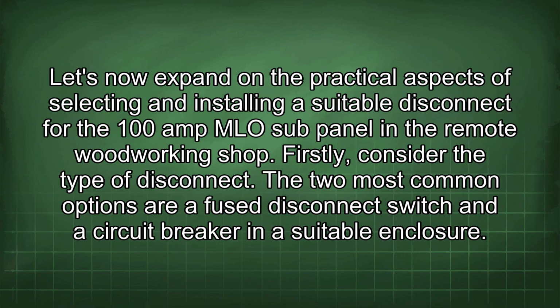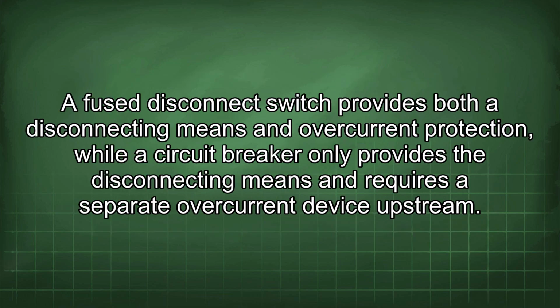Let's now expand on the practical aspects of selecting and installing a suitable disconnect for the 100 amp sub-panel in the remote woodworking shop. Firstly, consider the type of disconnect. The two most common options are a fused disconnect switch and a circuit breaker in a suitable enclosure. A fused disconnect switch provides both a disconnecting means and overcurrent protection, while a circuit breaker only provides the disconnecting means and requires a separate overcurrent device upstream.